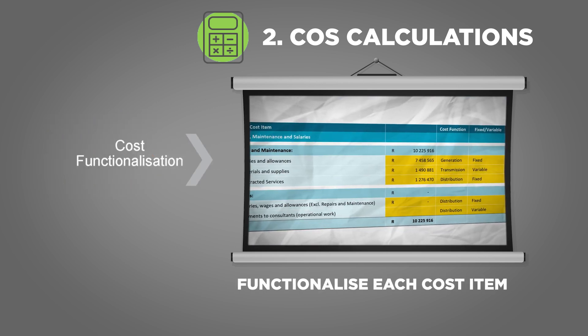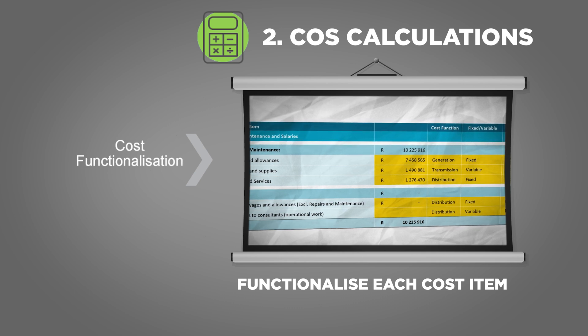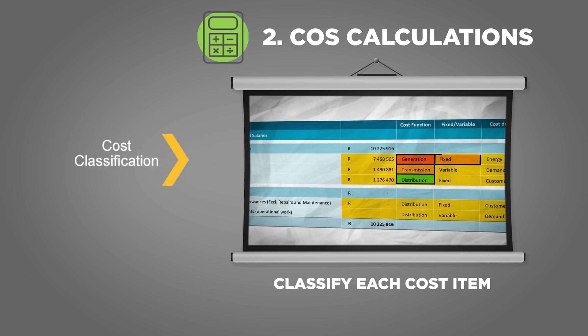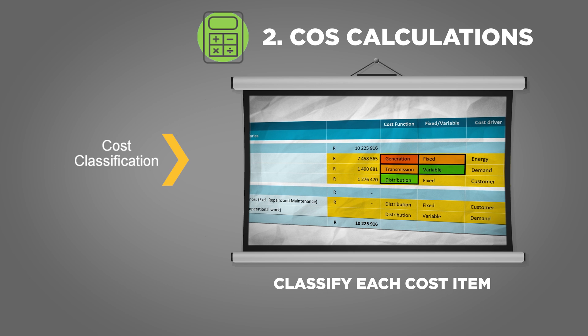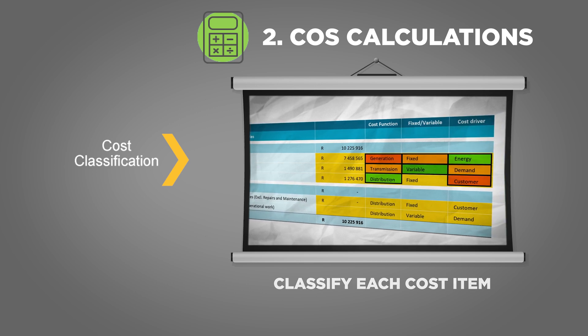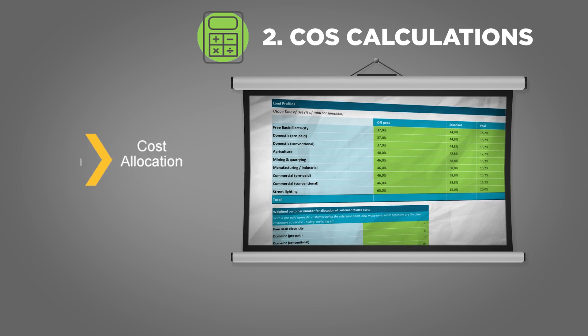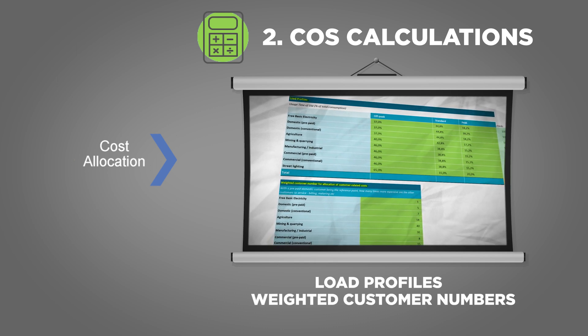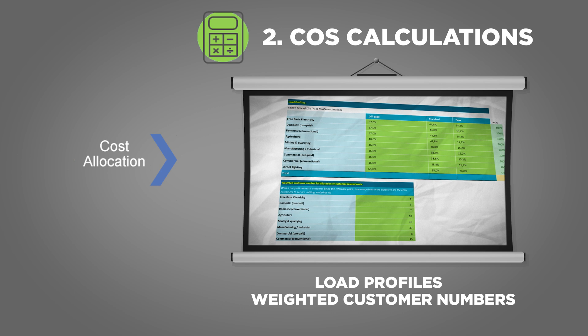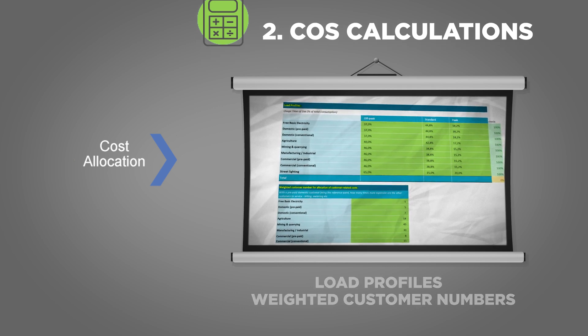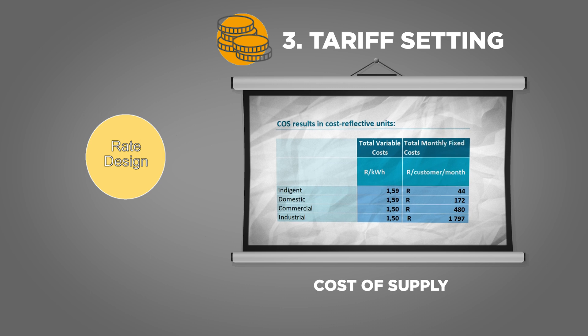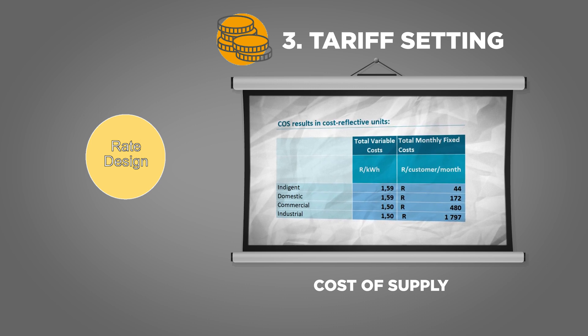Next is to functionalize each D-Form cost item as generation, transmission or distribution. Then they are classified as fixed or variable and according to their cost driver: energy, demand or customer. The cost groups are then allocated using the advanced data inputs, including load profiles and weighted customer numbers. Proxy data is provided in the tool and this can be improved if you have better data available. Now you will arrive at your cost of supplying each customer group with electricity. This is a key input into your tariff design, which is the final step of the cost of supply process.